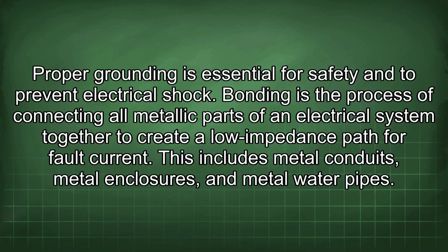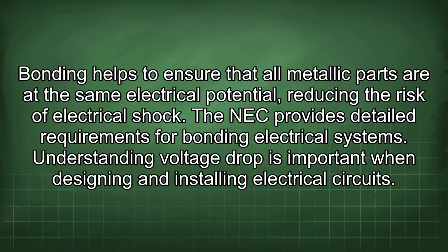Bonding is the process of connecting all metallic parts of an electrical system together to create a low-impedance path for fault current. This includes metal conduits, metal enclosures, and metal water pipes. Bonding helps to ensure that all metallic parts are at the same electrical potential, reducing the risk of electrical shock. The NEC provides detailed requirements for bonding electrical systems.